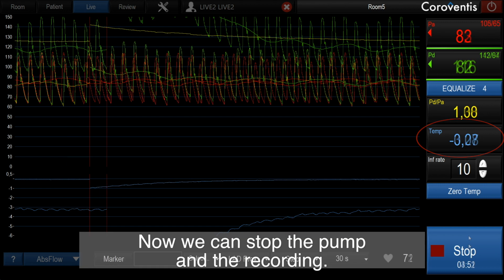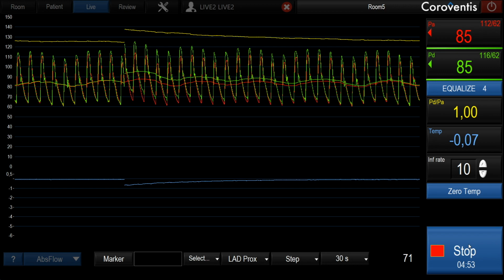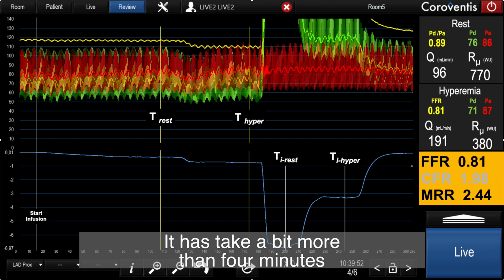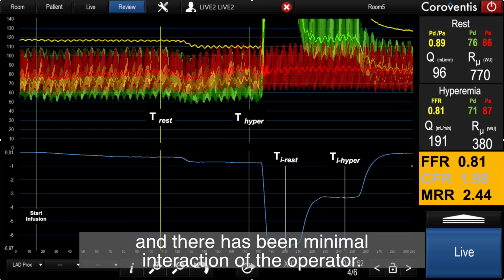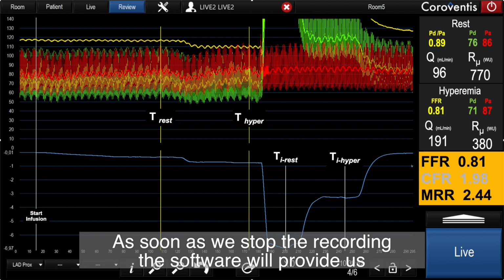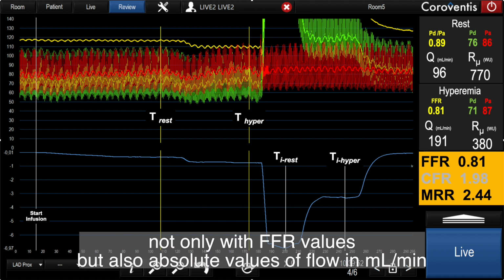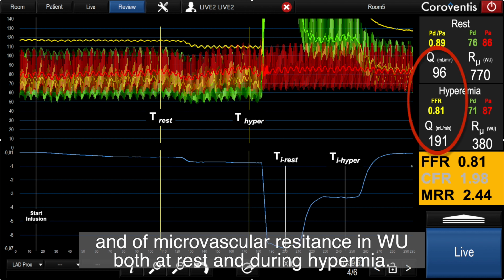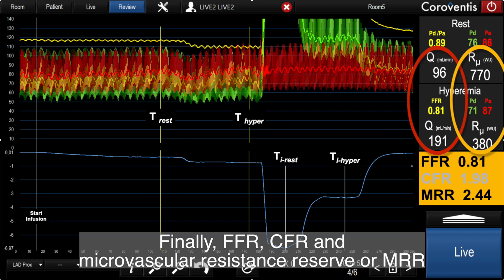Now we can stop the pump as well as the recording. It has taken a bit more than 4 minutes, and there has been minimal interaction with the operator. As soon as we stop the recording, the software will provide us not only with fractional flow reserve values, but also with absolute values of flow in milliliter per minute and of microvascular resistance in Wood units, both at rest and during hyperemia.